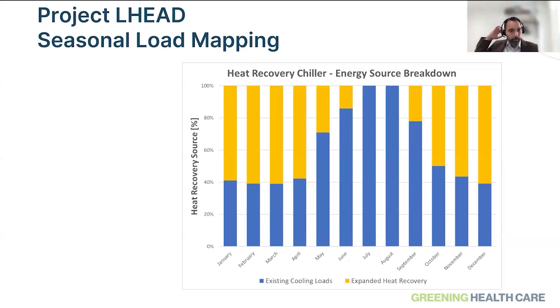Did you end up adding new coils for that whole system? No, we did not. What we did was, this runaround system was a glycol loop from exhaust to fresh air preheats, and we added a glycol to chilled water heat exchanger to this loop. So when the preheats do not need the full recovery capacity of that exhaust, we divert glycol through a chilled water heat exchanger and bring that heat back to the heat recovery chiller through the existing chilled water network. Chilled water is going everywhere in a hospital where there's a ventilation system generally already. So leveraging that network to get the heat back to a heat recovery chiller is an efficient way to do a project like this.